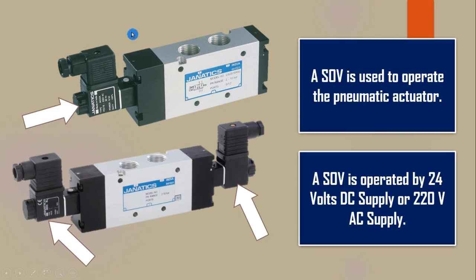The upper solenoid is known as a single coil solenoid because it has only a single coil, and the lower solenoid is known as a double coil solenoid because it has two coils. In the single coil solenoid, when supply is given it will open the valve, and when supply is not given it will close the valve. In the double coil solenoid, separate coils are used to open and close the valve.